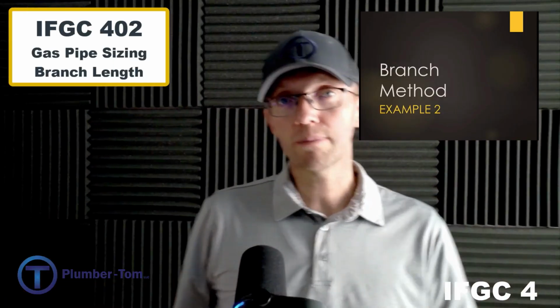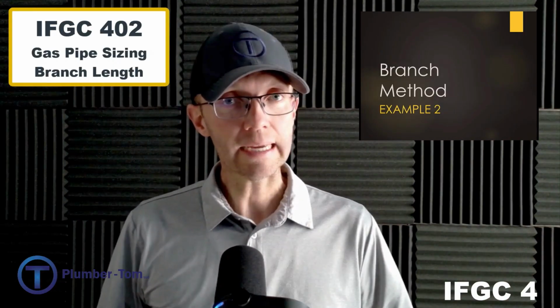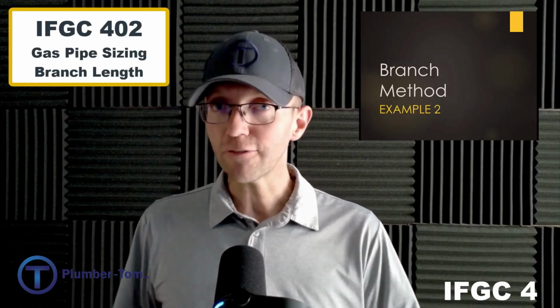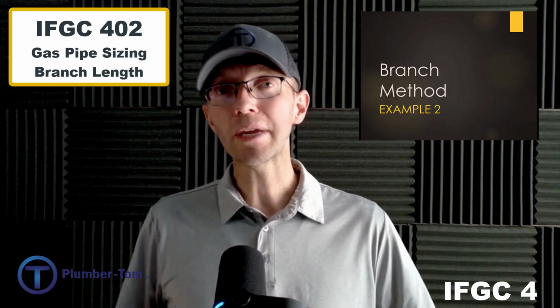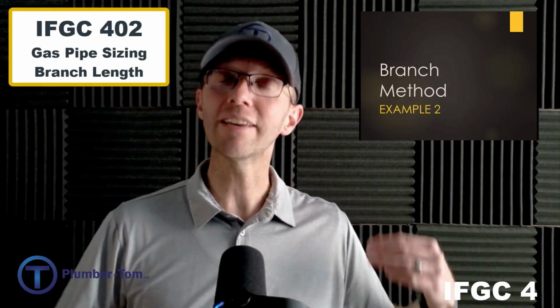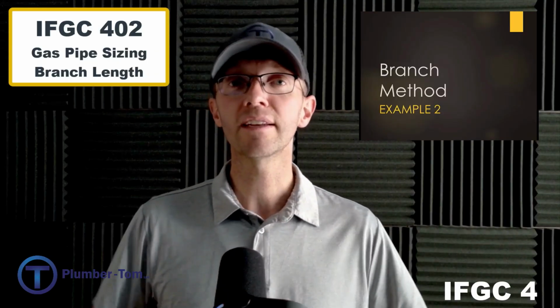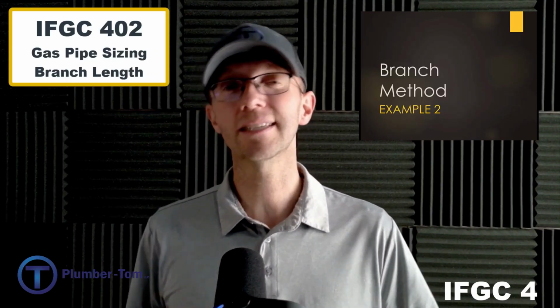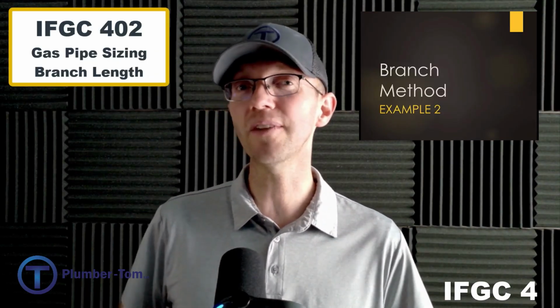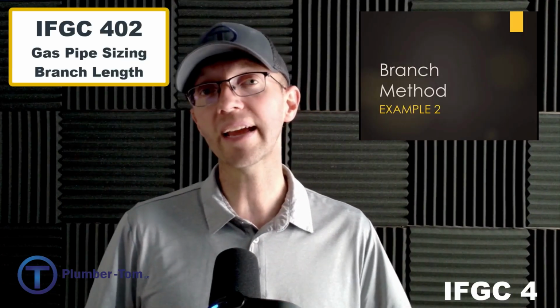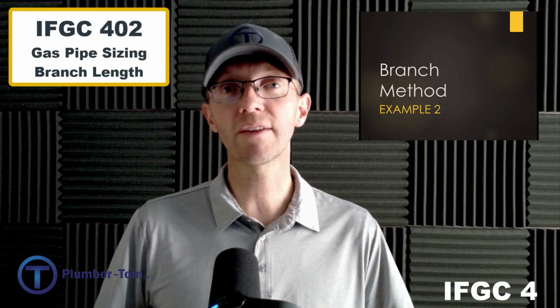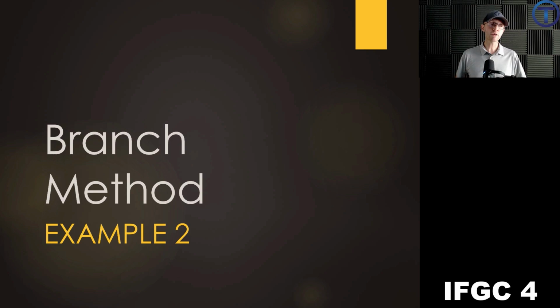All right, are you still with me? We've completed example 1, and hopefully you can see the difference with the branch length method. Not only were we using different types of pipes, but we were using different distances on our table to get the most precise system. Once again, not as conservative, but really quite accurate, and especially for our different types of pipe. Let's look at branch length method example 2.